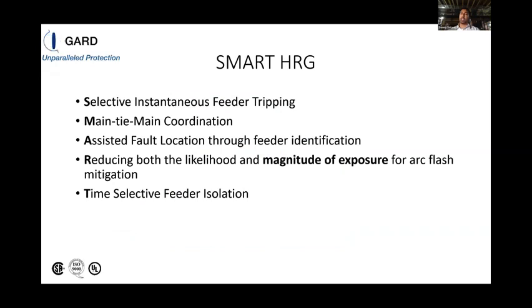Smart HRG is an acronym for Selective Instantaneous Feeder Tripping, Main-Tie-Main Coordination, Assisted Fault Location through Feeder Identification, reducing both the likelihood and magnitude of exposure for arc flash mitigation, as well as time-selective feeder isolation.